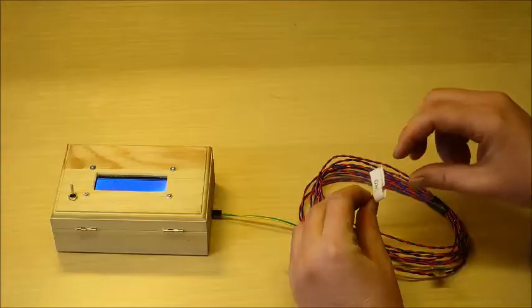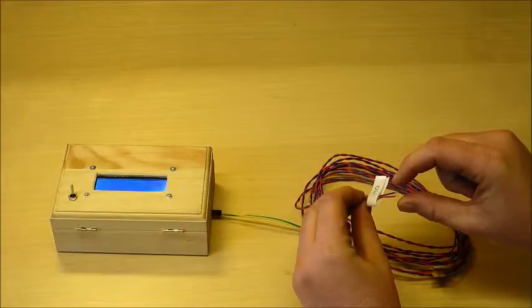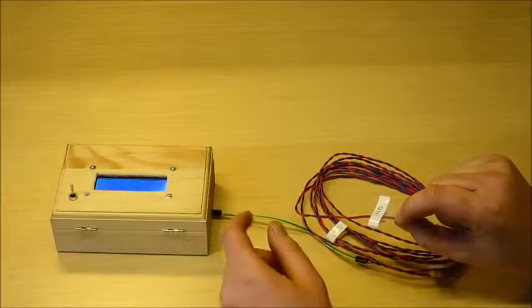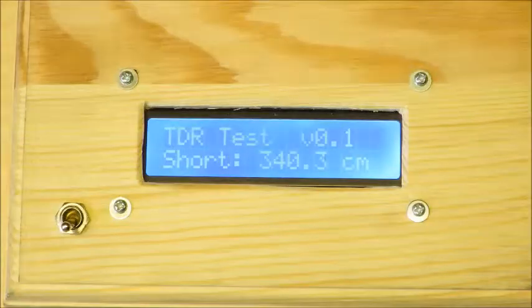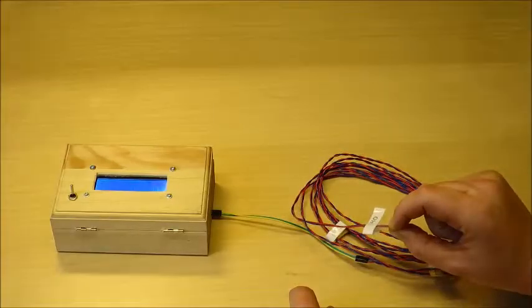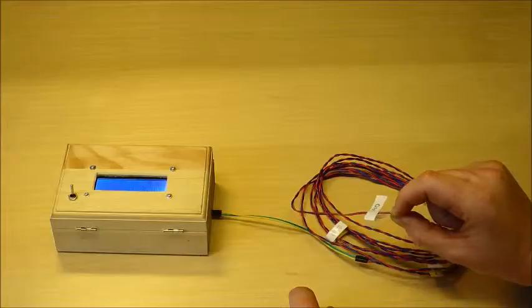As you can see here at some instances I have removed the isolation. If we now create that short circuit here, we can see on the display it displays how many cm away from the unit is this short circuit located.